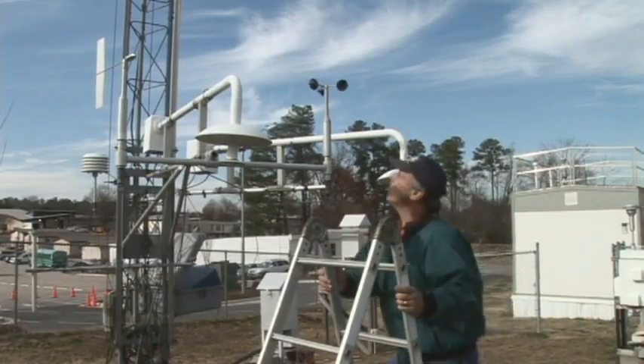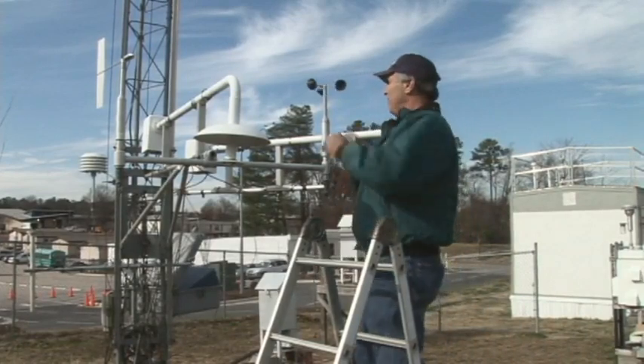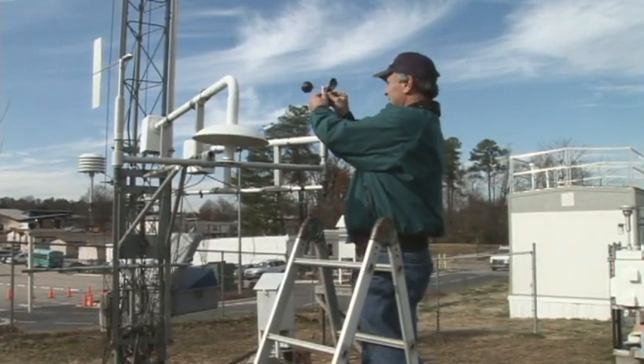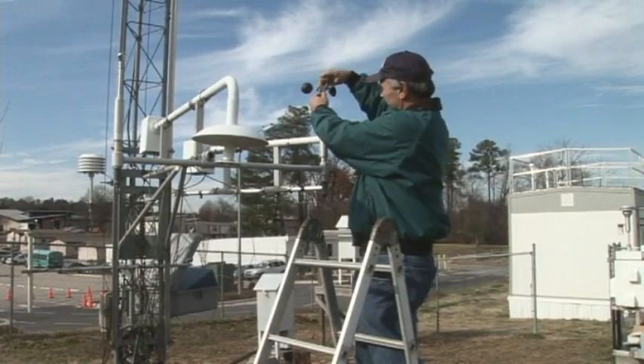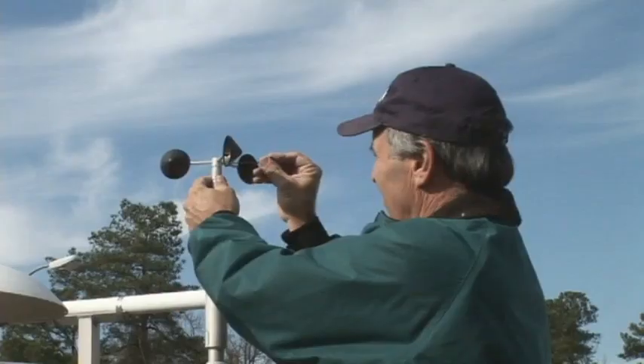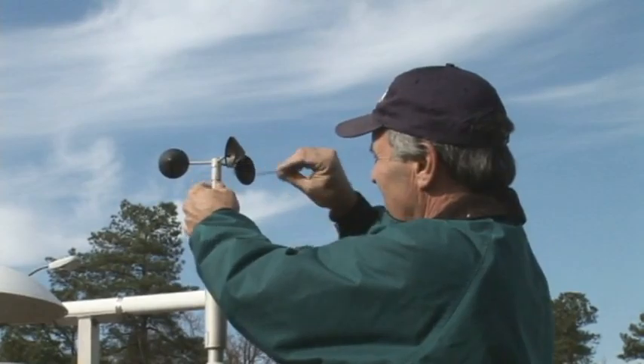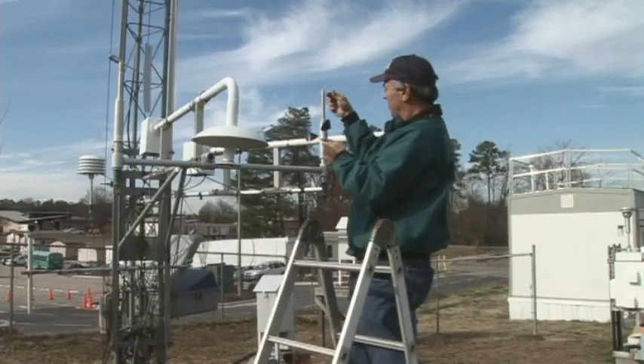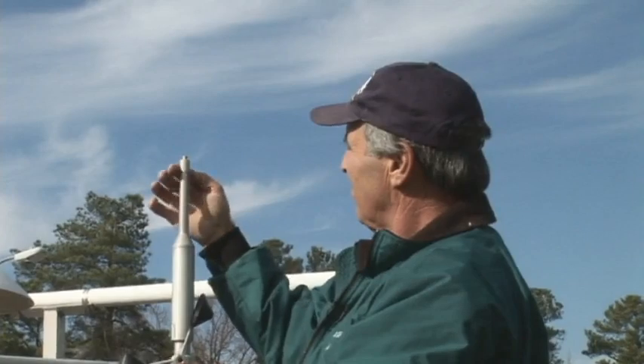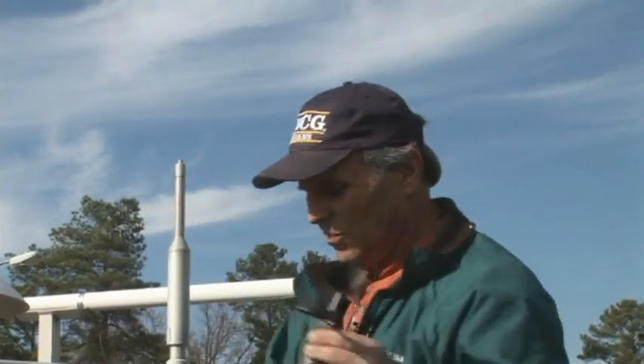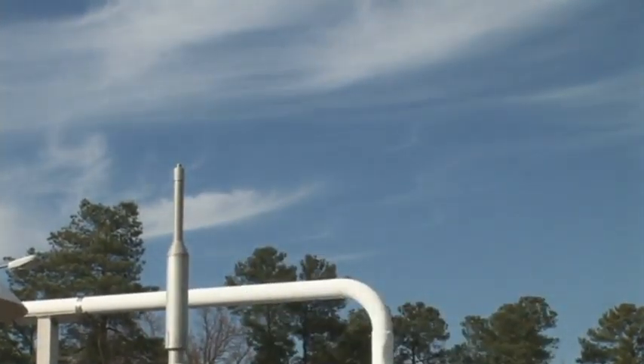It is now time to remove the wind speed anemometer cups. This is done by loosening the Allen nut with an Allen wrench that holds the cups to the anemometer shaft. The Allen nut and wrench will be supplied by the anemometer manufacturer. At this time, take the anemometer shaft between your thumb and index finger and turn it back and forth. Test to see if there is any drag or friction that you can feel. If so, the bearings may need to be replaced. We will quantify the drag of the bearings using a torque test, which will determine the starting threshold. We will perform this test later.